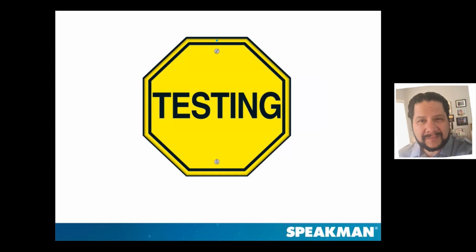Because I will tell you, when we go out and do these eyewash surveys on site, I would say 6 out of 10 do the regular testing, and that's it. So about 40% of these, on average, aren't doing it regularly, weekly. So again, remind the end users and the customers that it needs to be done. It needs to be a process.